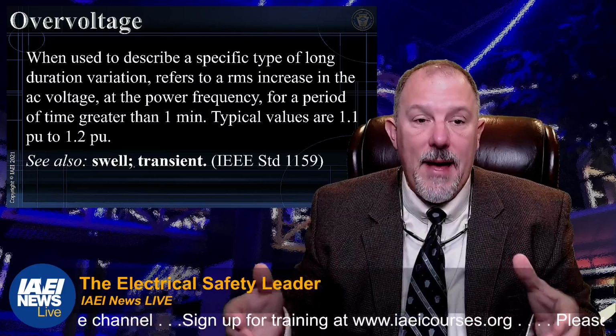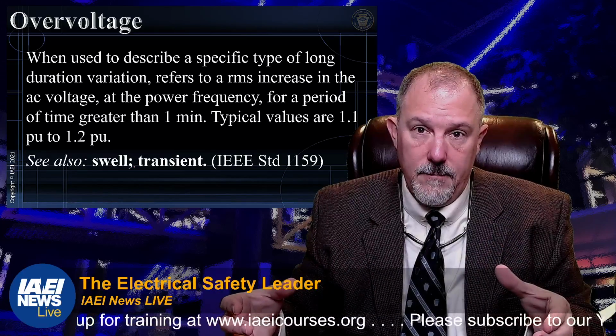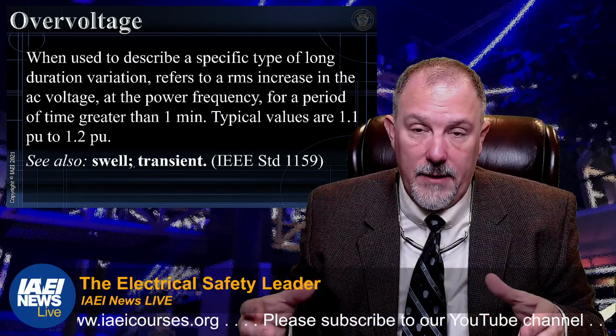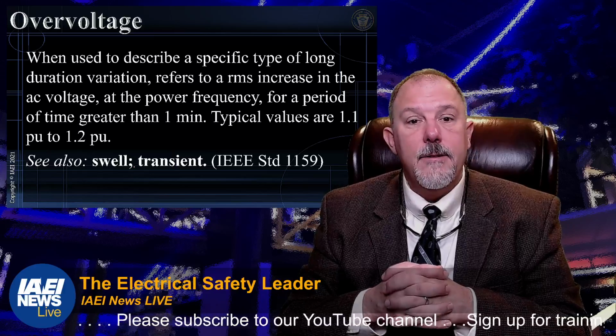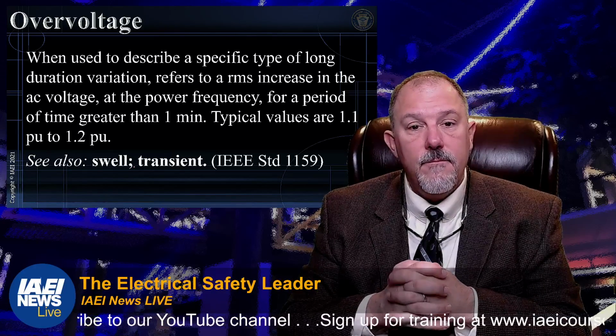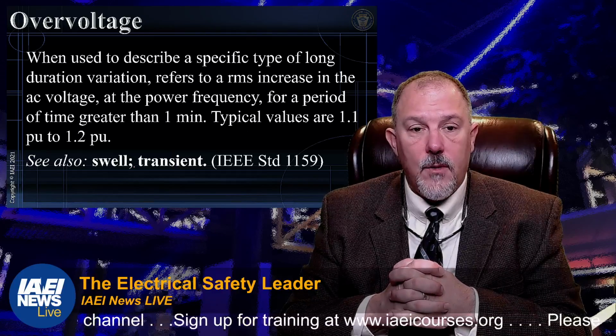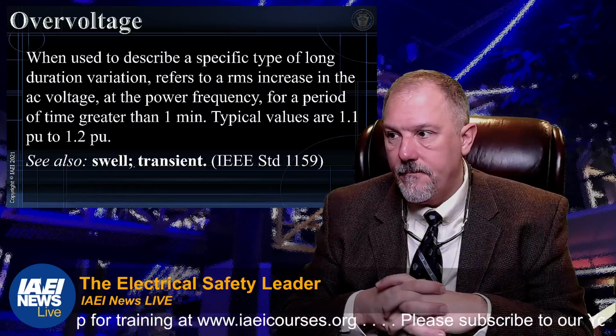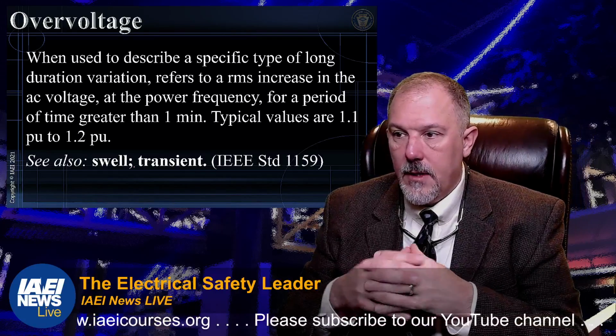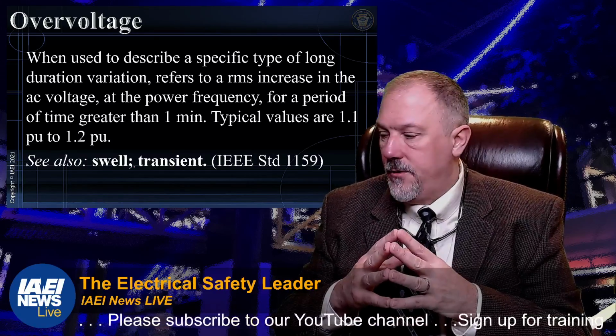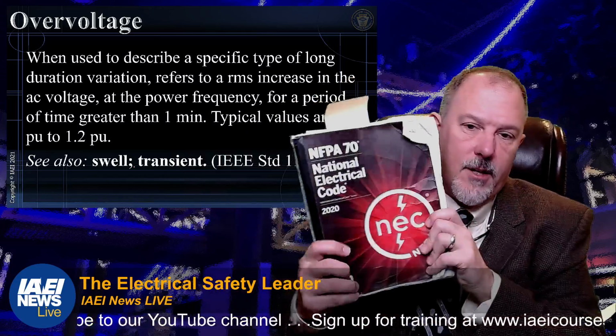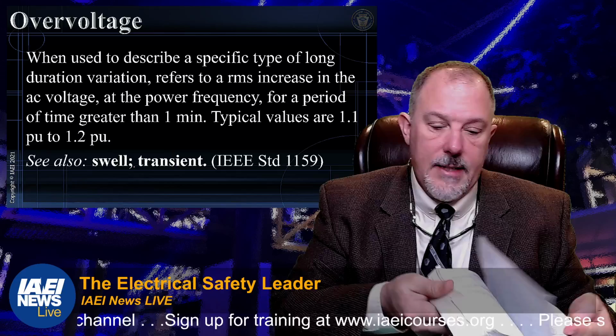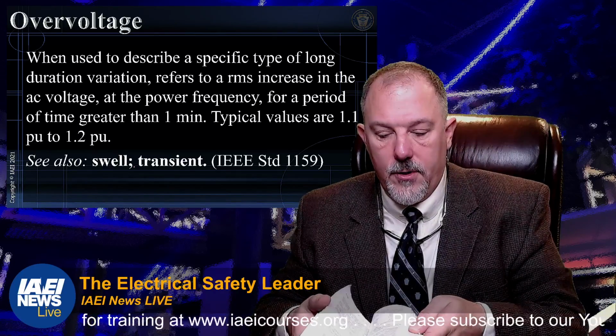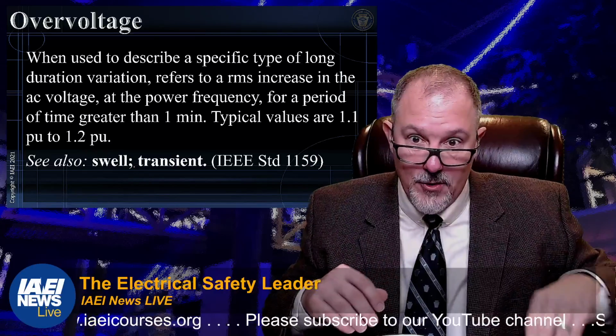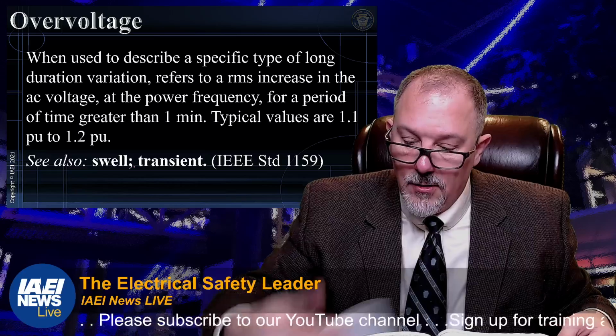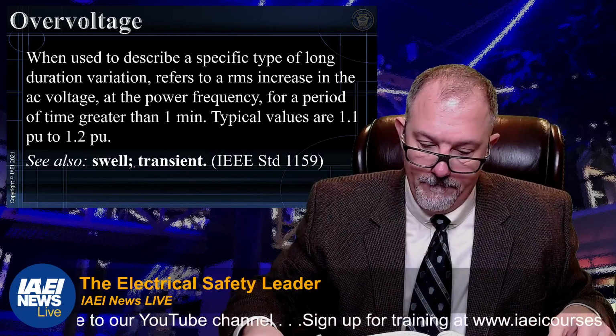Now think about it. It's an RMS increase in voltage, and RMS is root mean square. It's not a transient event. It's not a subcycle event. An overvoltage is typically greater than 1 minute, and it's an RMS value. We call it an overvoltage. Now, the way I think the National Electrical Code, and I'm talking about the 2020 code, if I think about what we did in this book, we created a new article in the 2020 Code Edition in Chapter 2. And we called it overvoltage protection.